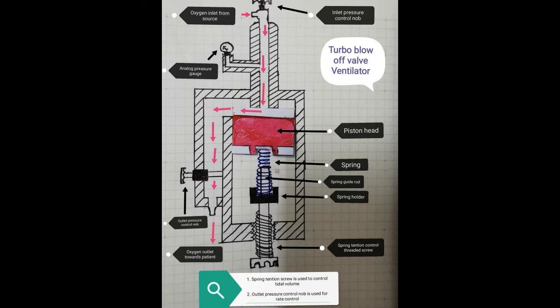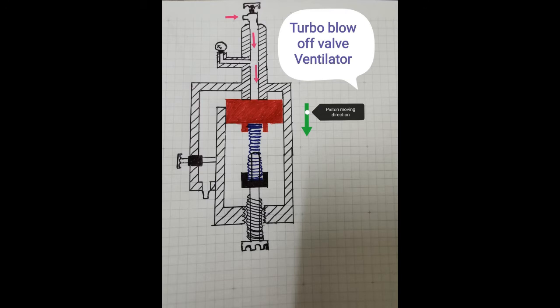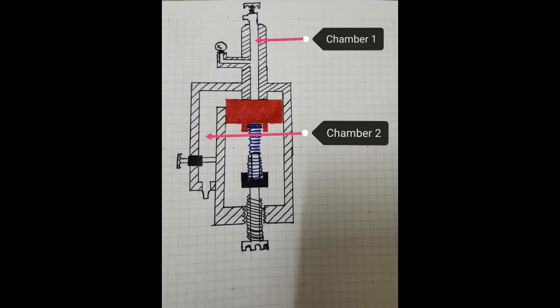The spring tension screw is used to control tidal volume, and the outlet pressure control knob is used for the rate control. We can attach an analog pressure gauge just before and just after the outlet pressure control knob to get the relevant readings. In this image, you can see that the valve is normally in closed position, and when we connect the oxygen inlet to the unit with controlled dispense rate by the inlet pressure control knob, the passage that you see from the inlet till the piston head would act as an expansion chamber, which I would call chamber 1.